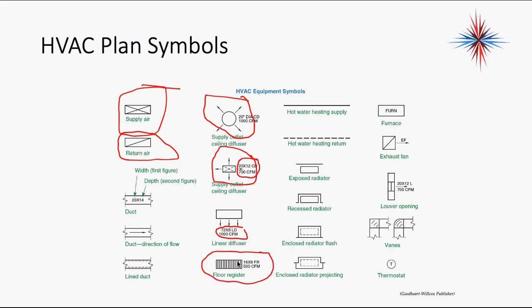Floor registers look a little different on a lot of prints — they put a lot of little lines through it. I normally use a supply air register symbol and just label it 'floor.' For those with boilers, a hot water heating supply is a single pipe, and a dotted line is the hot water return to the boiler. Supply goes away from the boiler; return brings water back to the boiler.